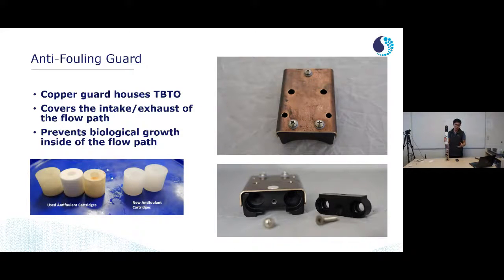When these are spent, or if you deploy this without anti-fouling cartridges, you'll still get good data, but if you're in a high biofouling area, your results are going to vary. So highly recommend deploying it. It's kind of hard to tell exactly how spent a given antifouling cartridge is. If you look at this picture on the left side, we have used antifouling cartridges where they have sort of varying looks when they are spent. But on the right side, we have brand new antifouling cartridges. It's hard to determine these visually. We recommend replacing them about every year or so. They should last for the entirety of your deployment.